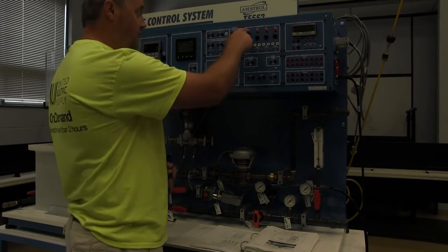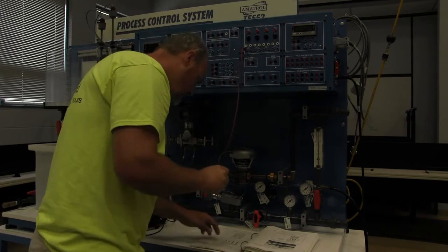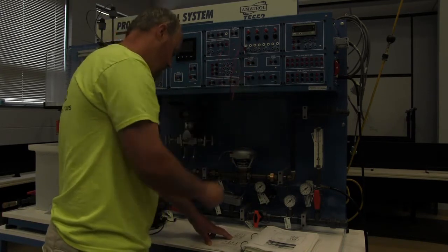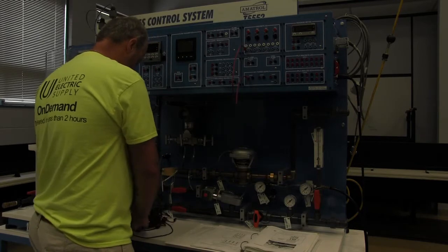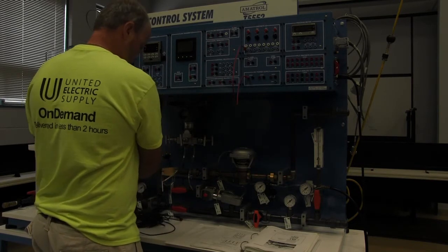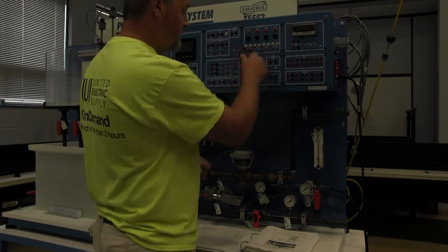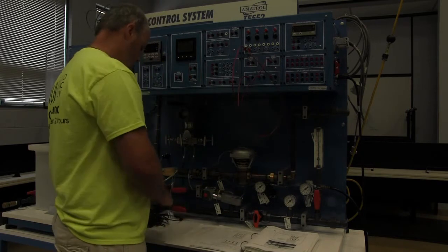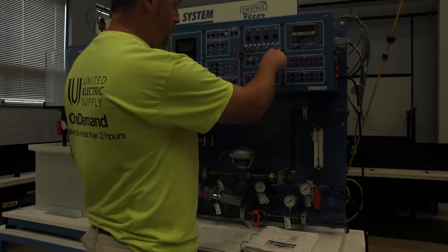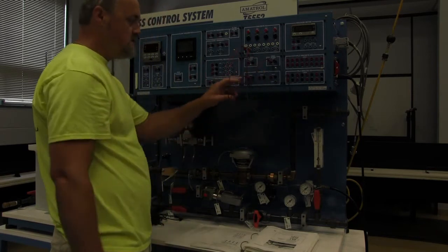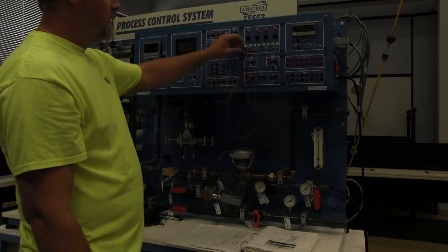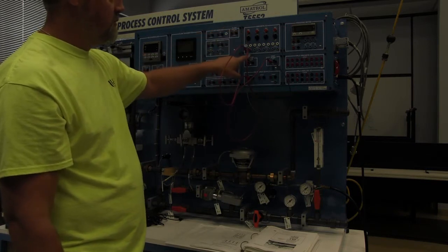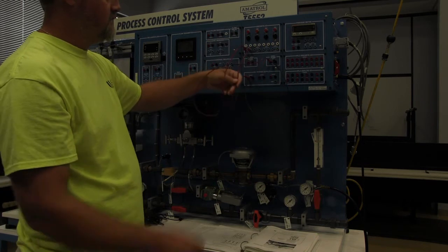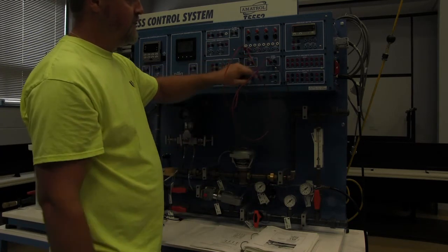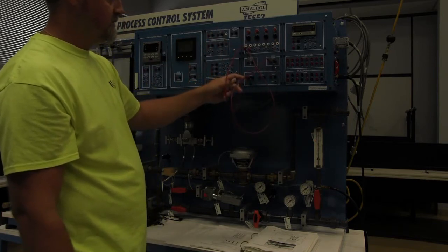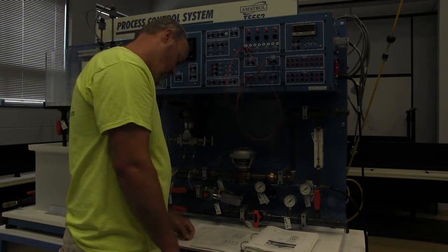From selector switch 1, we're going to go to the DC power supply. From the other side of selector switch 1, we will be going to the pump. From the negative of the pump, we will be going back to the negative of the power supply. So basically what you have here is 24 volts going to the selector switch, which is normally open. When you flip the switch, it will close it. Can make the 24 volts go to the circulator pump, and then the circulator pump needs a negative to complete the circuit. It is now wired as shown.